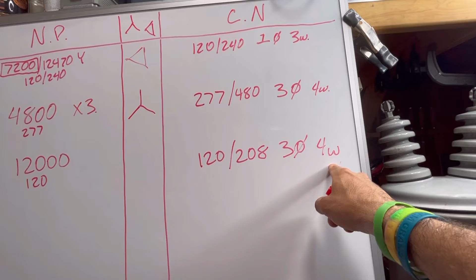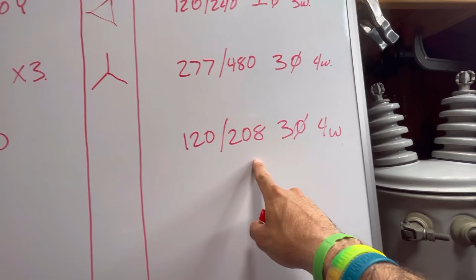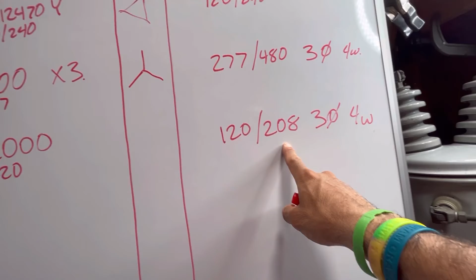Delta hookup, right? This is my phase-to-phase voltage on that circuit. My transformer needs the same number. Therefore, the only way to hook it up is phase-to-phase, or delta. Secondary. So customer needs 120/208, 3-phase 4-wire. My secondary output is 120. So, delta divide. Does 120 divide evenly into 208? No, it does not. It's going to be a Y hookup.